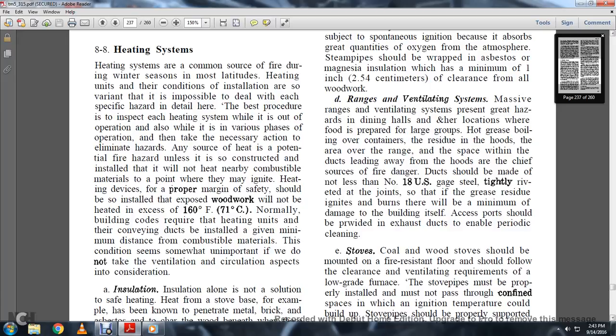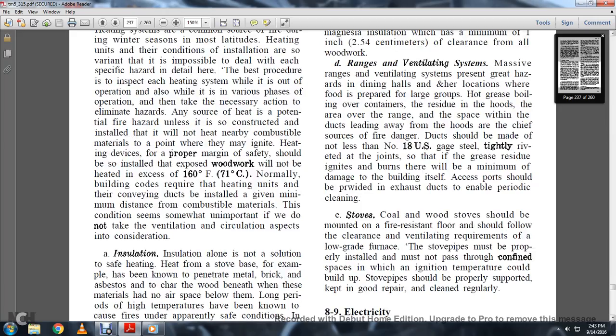is the chief source of the fire danger. The duct should be made of not less than number 18 U.S. standard gauge, sealed tightly with riveted joints, so that if the grease residual ignites and burns, there will be minimum damage to the building itself. Access ports should be provided in the exhaust ducts to enable periodic cleaning.